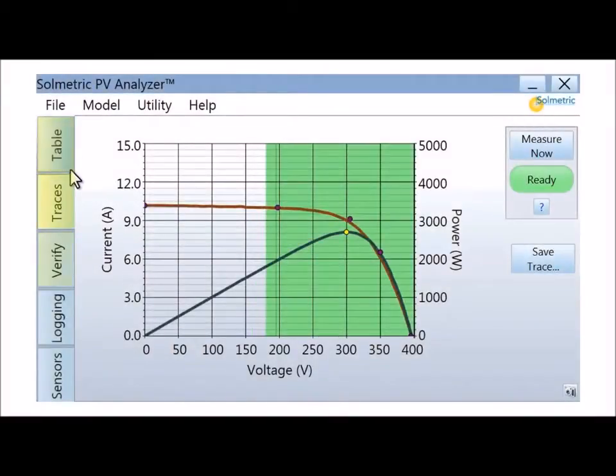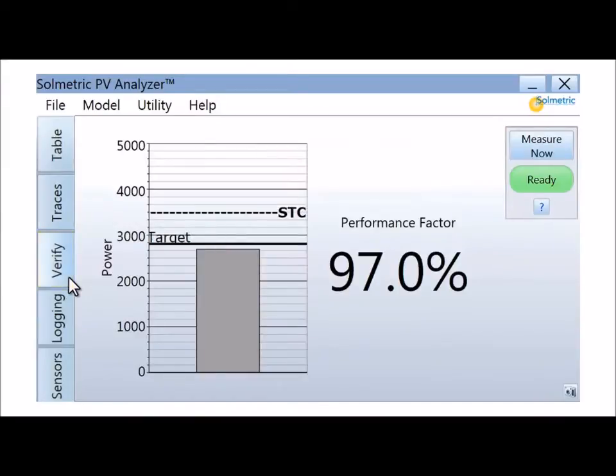The results can be viewed in various formats. The verify tab shows a simple percentage value that represents the measured power output as a percentage of the power predicted by the performance model. This percentage is called the performance factor and it provides a quick and simple method of performance verification.